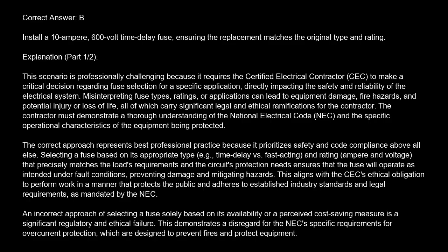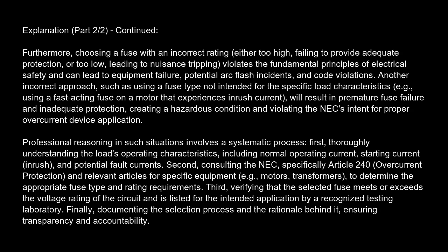An incorrect approach of selecting a fuse solely based on its availability or a perceived cost-saving measure is a significant regulatory and ethical failure. This demonstrates a disregard for the NEC's specific requirements for overcurrent protection, which are designed to prevent fires and protect equipment. Furthermore, choosing a fuse with an incorrect rating, either too high, failing to provide adequate protection, or too low, leading to nuisance tripping, violates the fundamental principles of electrical safety and can lead to equipment failure, potential arc flash incidents, and code violations.